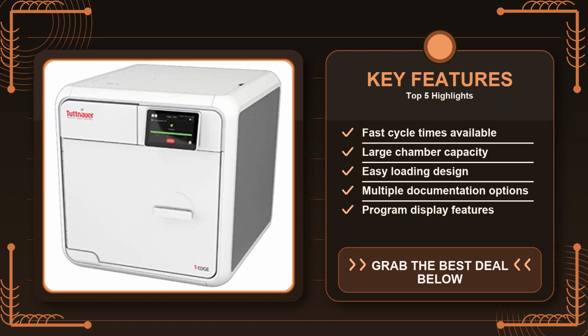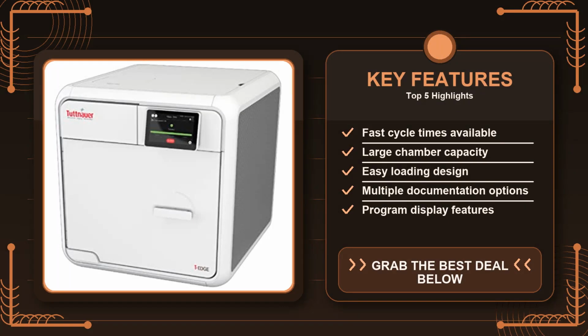The machine also supports multiple program presets, allowing you to switch between fast cycles for unwrapped instruments and slower, more thorough cycles for wrapped items, something you'll appreciate if you sterilize a mix of items daily. But no device is perfect, and this is where the practical drawbacks start to surface. The first thing I noticed is that the unit, while fully automatic, still requires you to monitor water levels manually.